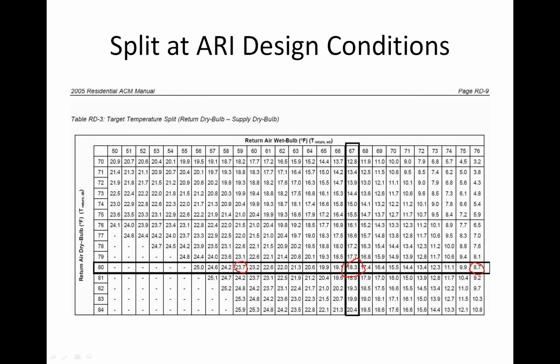The reason the temperature hasn't changed is because we're removing such massive amounts of humidity from the air that there isn't much energy going to drop the temperature yet, right? The air feels cooler coming out of the register, but not very much cooler than it is going in. But if you went downstairs and pulled the condensate drain off, you'd find a quarter-inch stream of water pouring out of the evaporator coil, because all the energy is going to convert its latent heat energy, or hidden heat energy, to convert that water vapor to water.